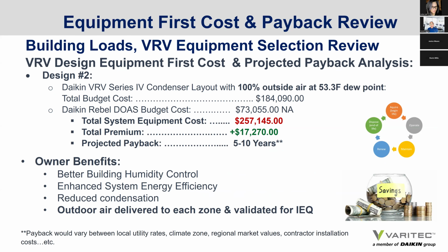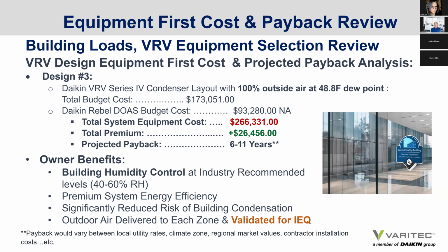If we look at design scenario number two, total equipment cost was $257,145. That's a premium of $17,270 with Daikin's projected payback of 5 to 10 years. But here you have better building humidity control, enhanced system energy efficiency, reduced condensation, and verifiable, validated indoor air, outdoor air delivered and supplied to each zone.